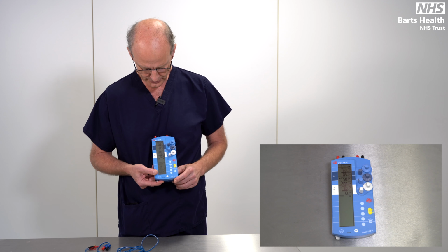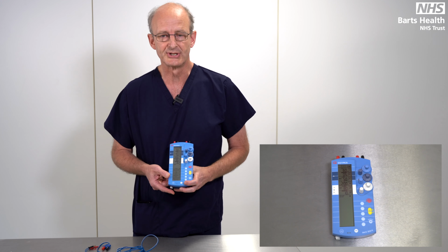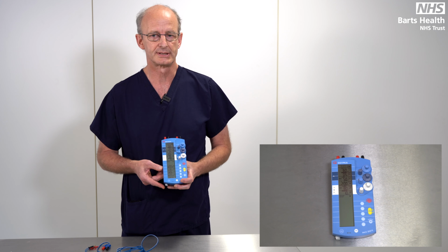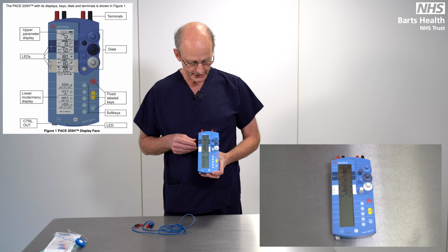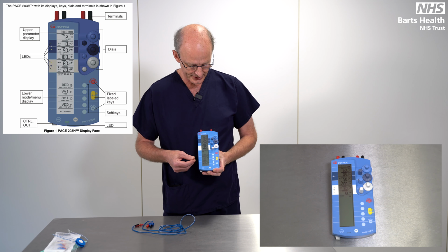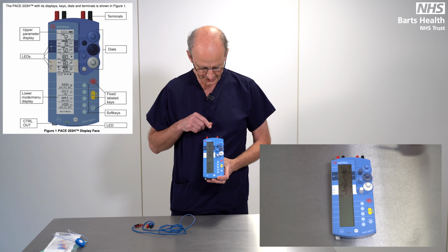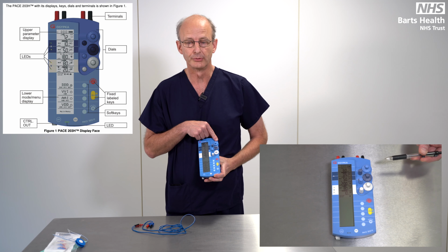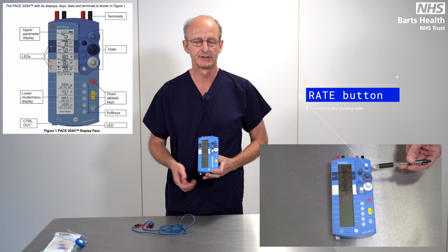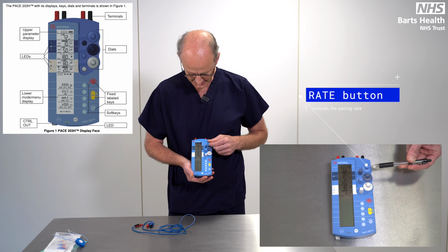So we'll press that now, and that will then show us the settings that the pacing box is set to. So if we work our way down the controls on the right hand side of the pacing box, what we can see first of all is the big blue knob at the top is the rate button that controls the rate the pacemaker is set at.